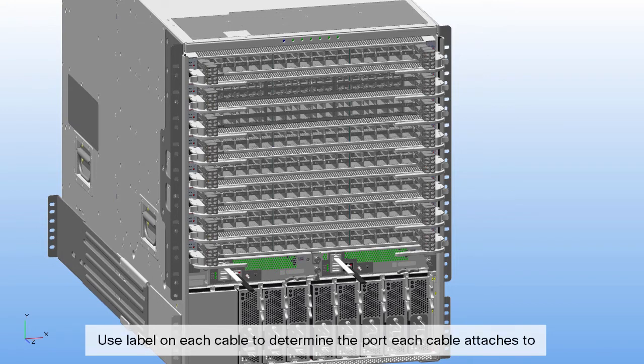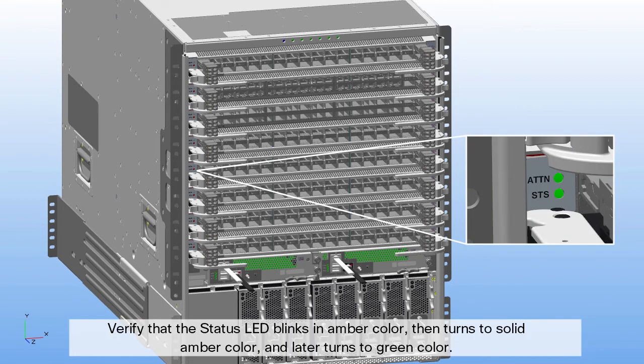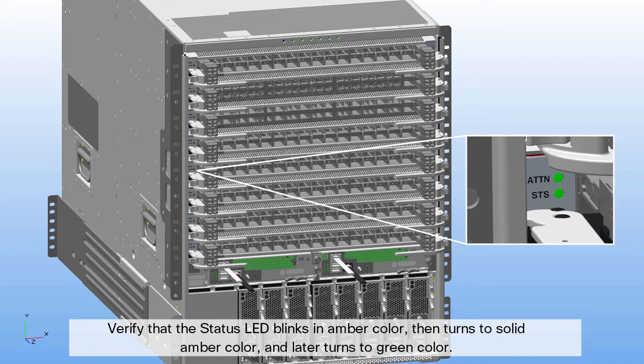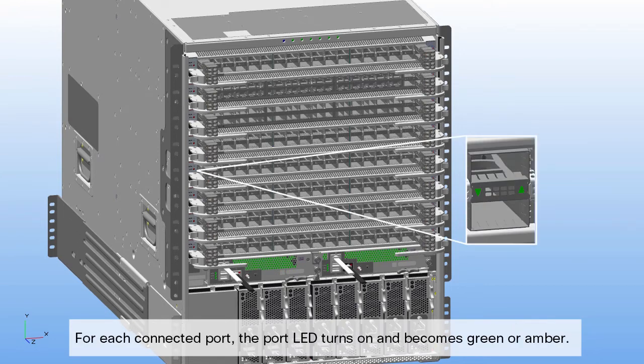Use the label on each cable to determine which port each cable attaches to. Verify that the status LED blinks in amber color, then turns to solid amber color, and later turns to green color. For each connected port, the port LED turns on and becomes green or amber.